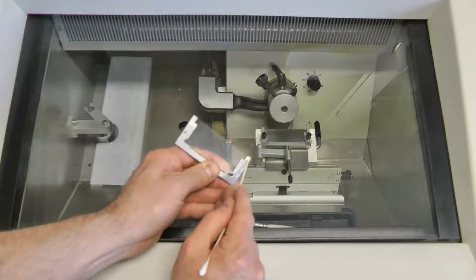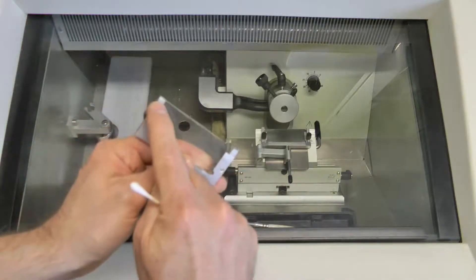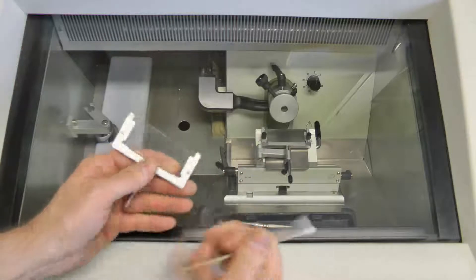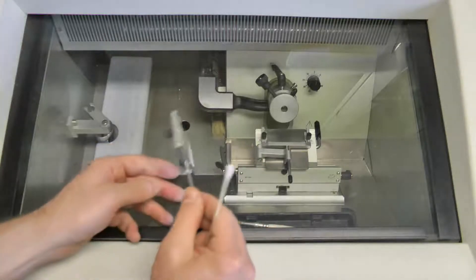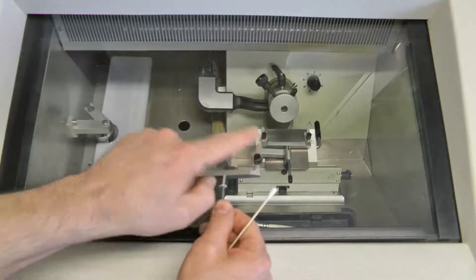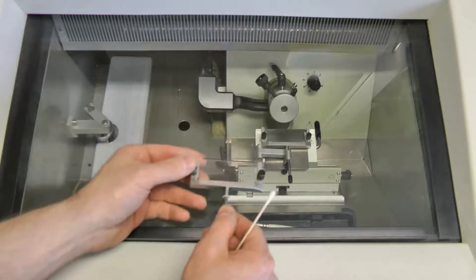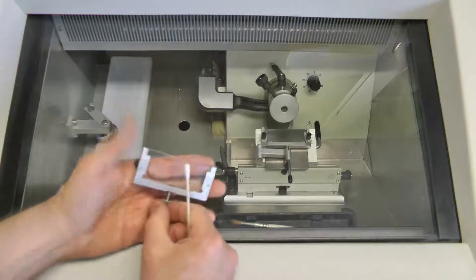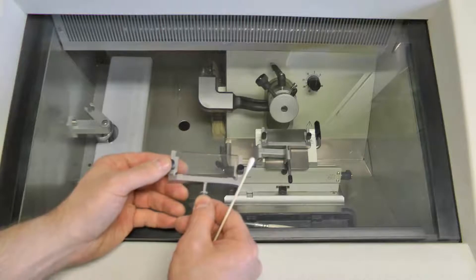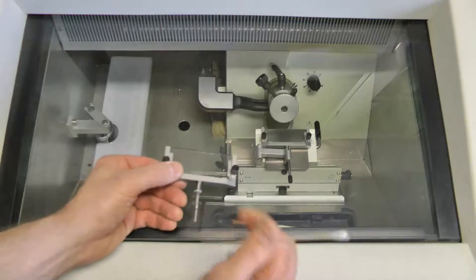You can see the stick here is catching in this little groove right here. So if you have a Leica, probably just flip your anti-roll plate over and you'll see with time this groove starts to form. Because of the arc of it coming down, the right-sided one tends to get a little bit more abused. So what happens with time is not only does the gap decrease, but it becomes a little bit skewed in the sense that your gap is uneven.